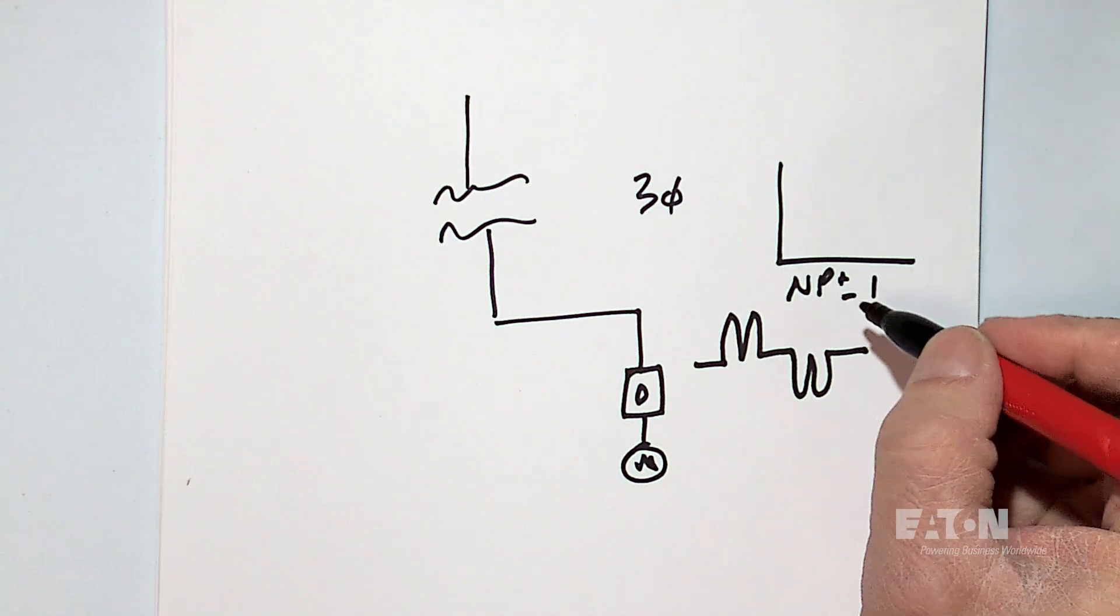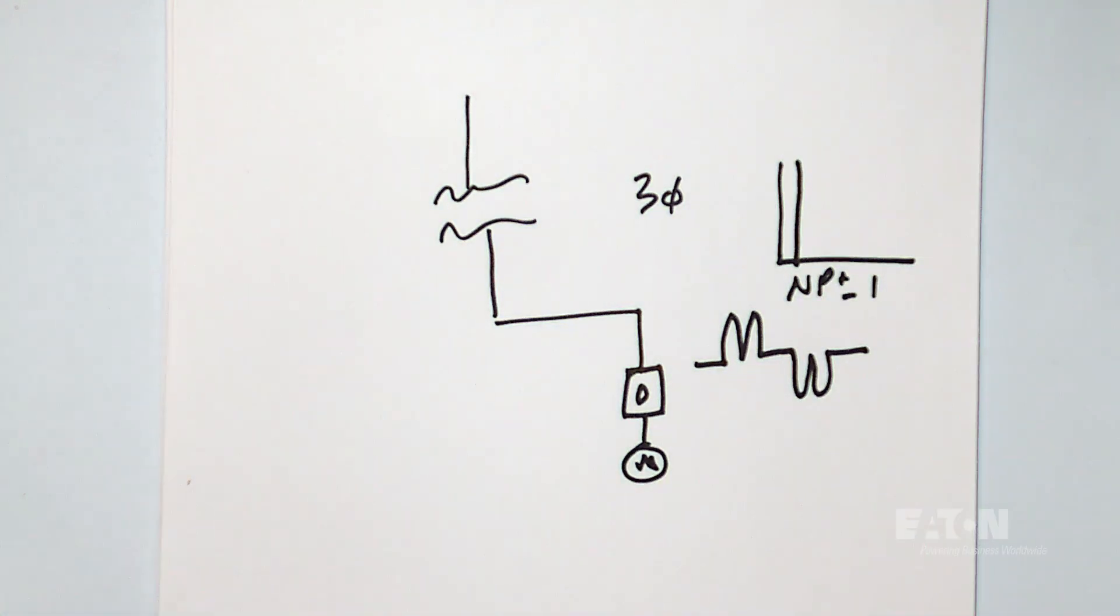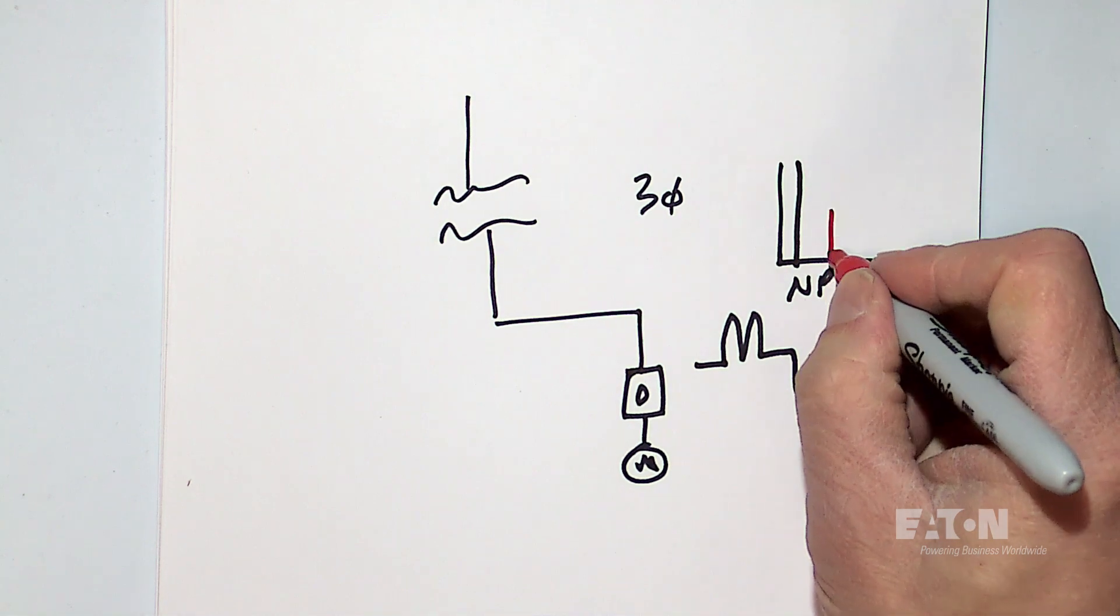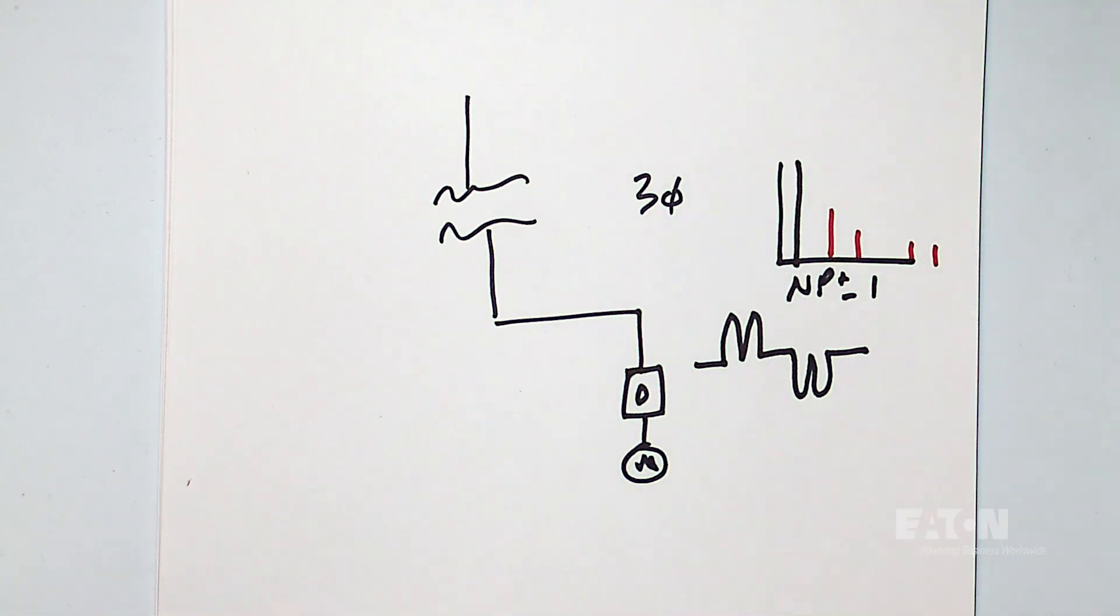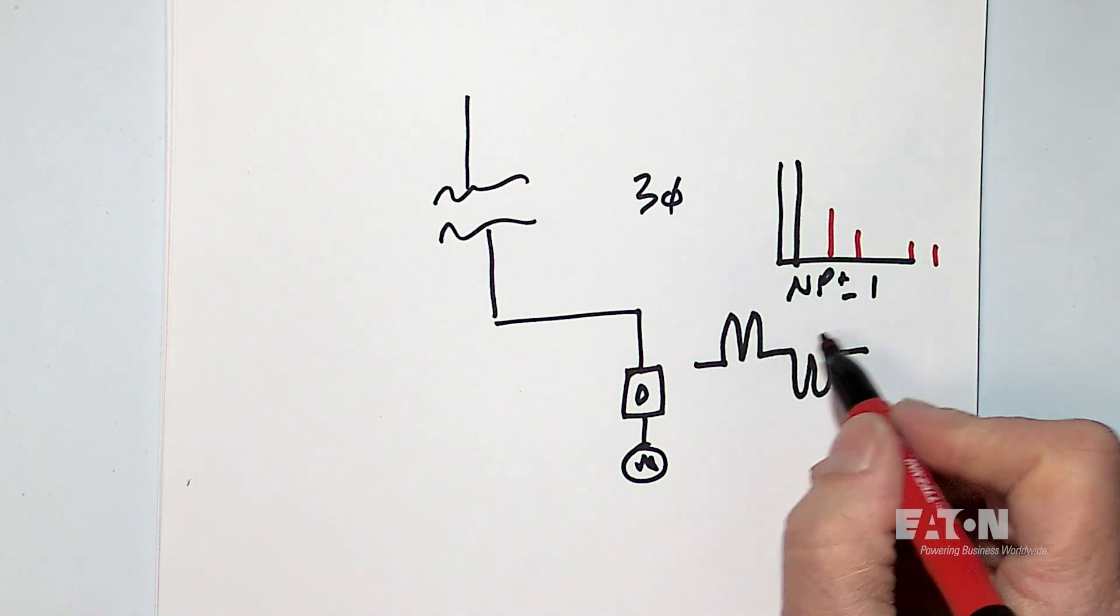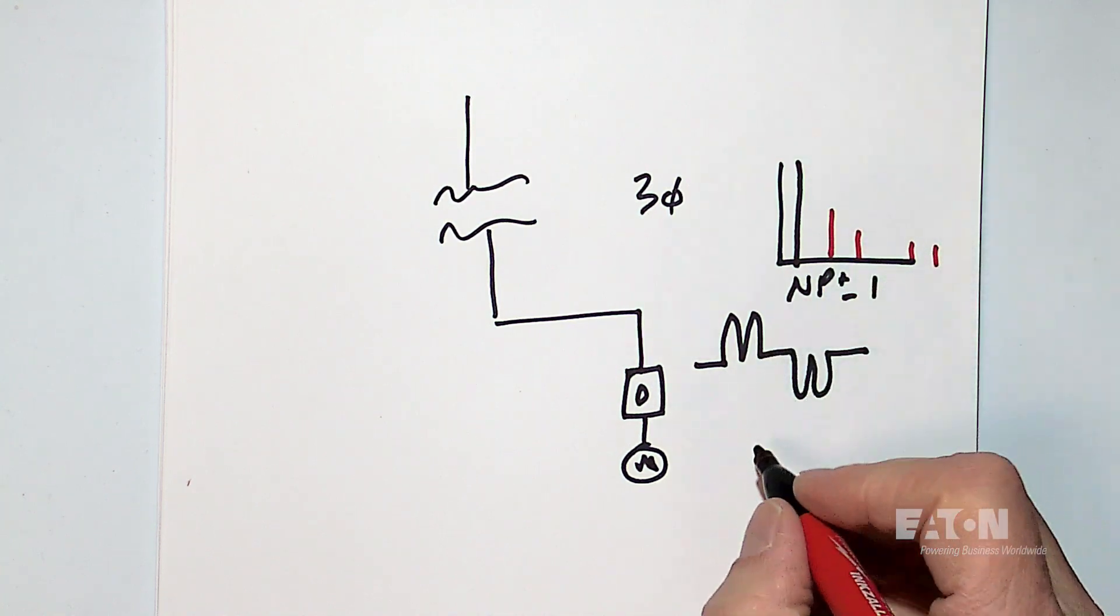So I have 60 hertz, then I have fifth harmonic, seventh harmonic, eleventh harmonic and thirteenth harmonic. That's pretty characteristic. The shape of these waveforms and the magnitude of this corresponds.